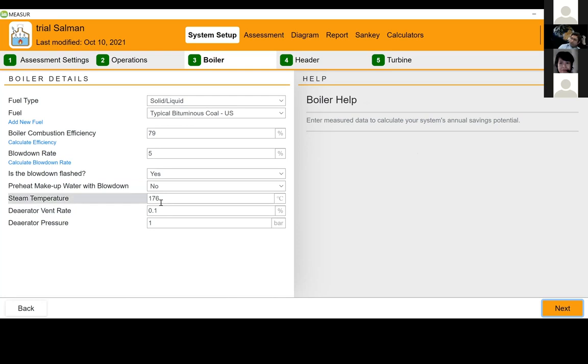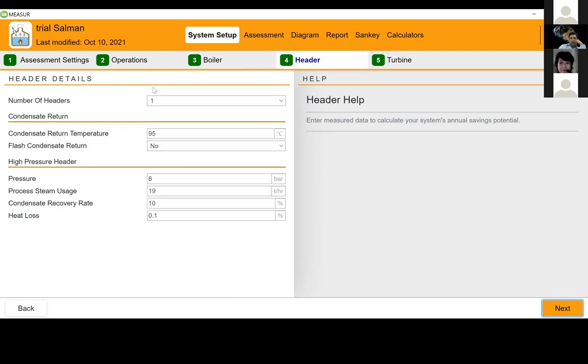Steam temperatures were 176 degrees. Deaerator vent rate was 0.1%. And the deaerator pressure was 1 bar. So it was actually 1 bar gauge, not 1 atmosphere. Then we went forward. I applied the header. So there was only one header. The condensate return temperature was 95%, and they were not flashing the condensate. So it was directly going to the deaerator and condensate recovery tank.